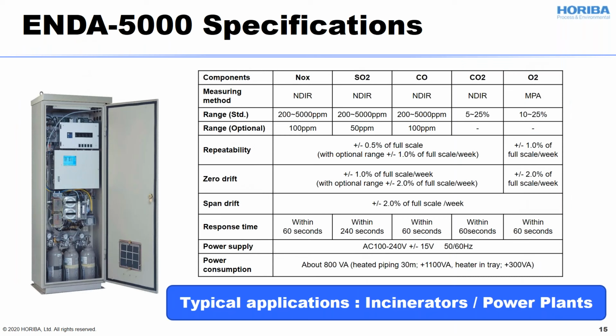All right, for the general specification, NDIR NOx range starts from 200 ppm to 5000 ppm. SO2 starts from 200 ppm to 5000 ppm, and CO starts from 200 ppm to 5000 ppm, and CO2 is from 5 to 25%, and O2 is from 10% to 25%, which is a very common specification. And you can go to the option range if you need to measure a lower range, like 100 ppm for NOx, 50 ppm for SO2, and 100 ppm for CO.